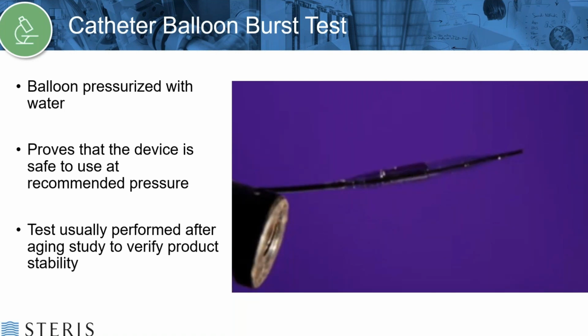So the first example of a test I'll show here is catheter balloon burst, and this test applies pressure to the balloon. We are proving that the device can withstand burst pressure, but also that it is burst pressure capable over time.